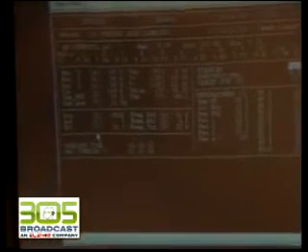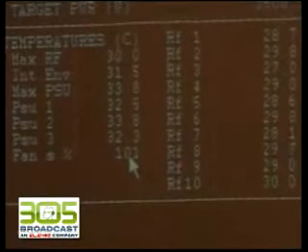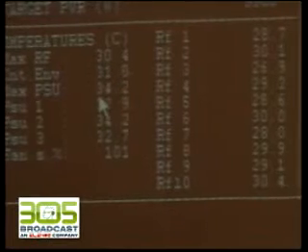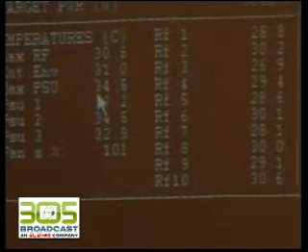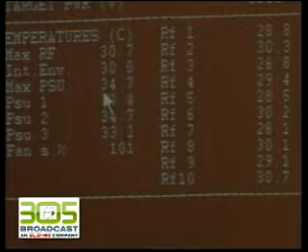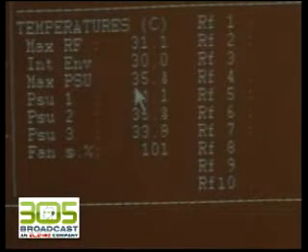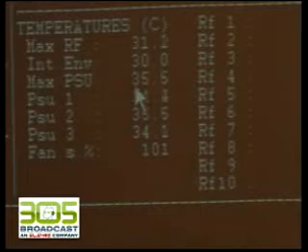And proceed to analyze the behavior of the plant in a normal environment, that is to say, with an air supply. The first thing we notice is that when we turn the equipment on, the fans also start at 100% and will always do so. It immediately starts to check the temperature of the power sources and of the radio frequency area. We'll see now how in a few minutes the fans will be working at a speed that is too fast considering the actual room temperature. You will notice how the transmitter detects this speed excess and slows it down.